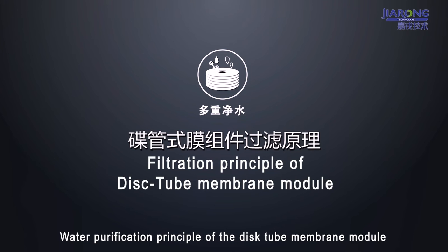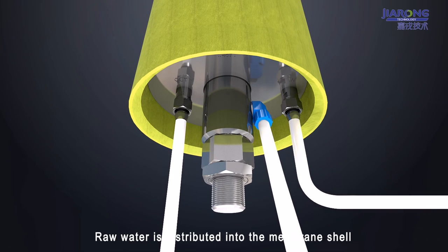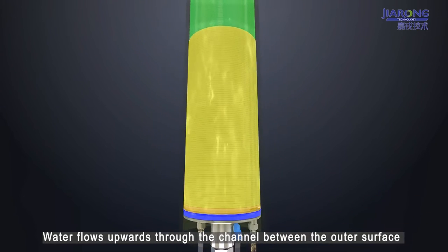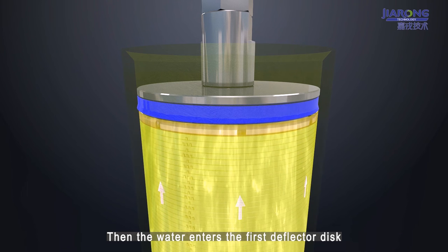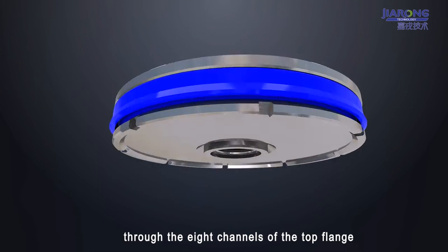Water purification principle of the disc tube membrane module. Raw water is distributed into the membrane shell through the inlet. Water flows upwards through the channel between the outer surface of the deflector disc group and the membrane shell. Then the water enters the first deflector disc through the 8 channels of the top flange.